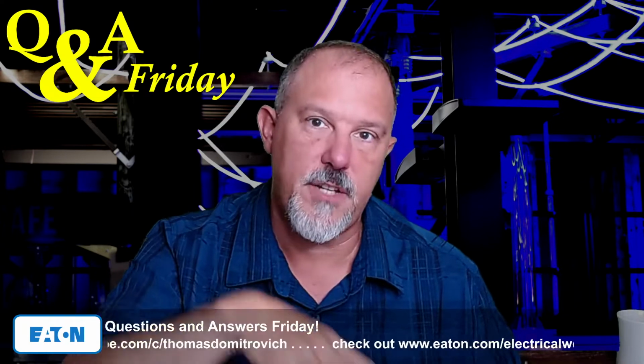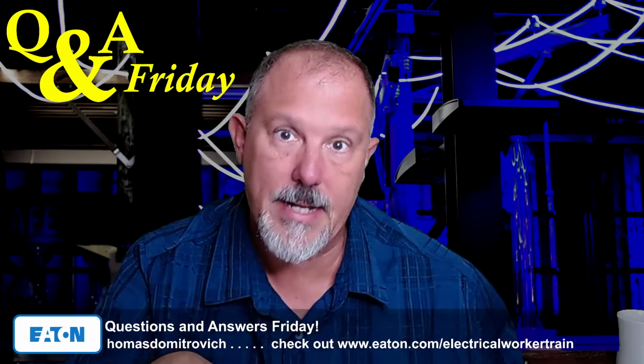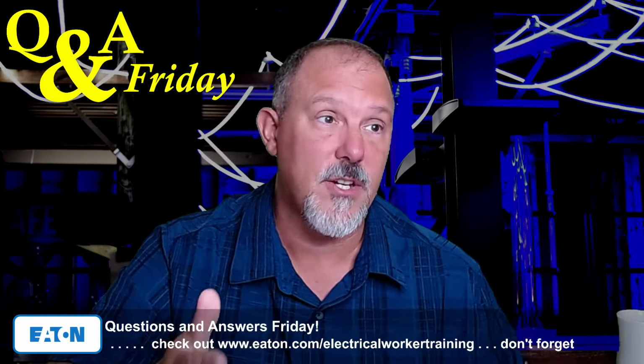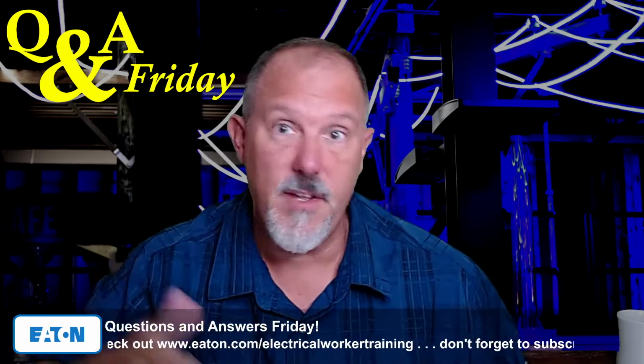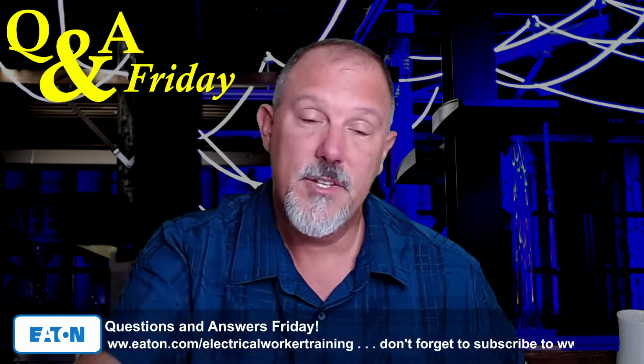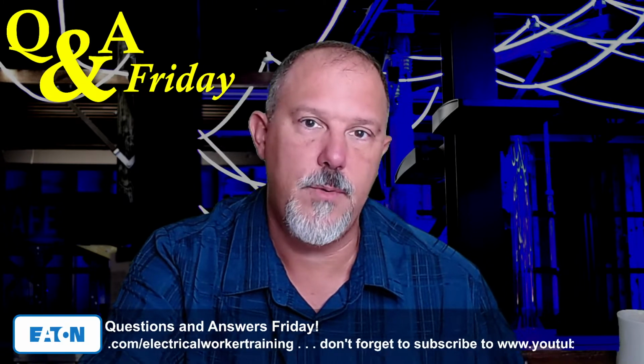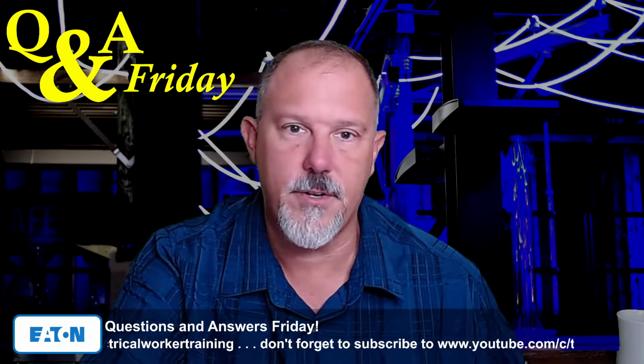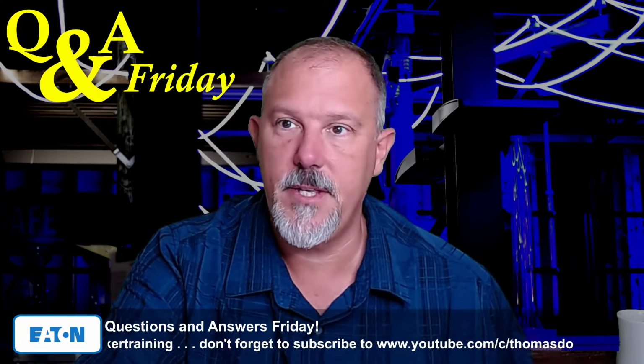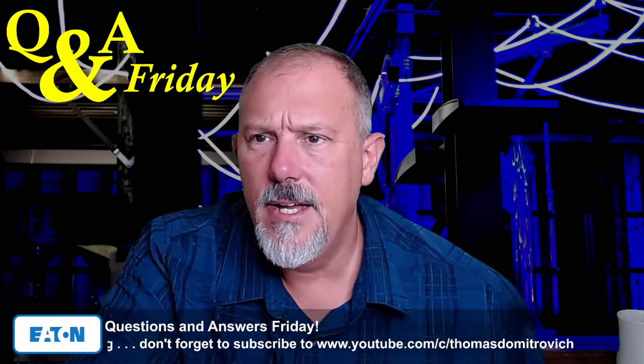So I think when you run your calculations, if you're using IEEE 1584 the way it is, and this is service entrance, well, it's not service entrance equipment. It's any circuit breaker now 1,000 amps and above for the 2023 code cycle. So yeah, you've got to do your homework. It's gonna be a challenge.